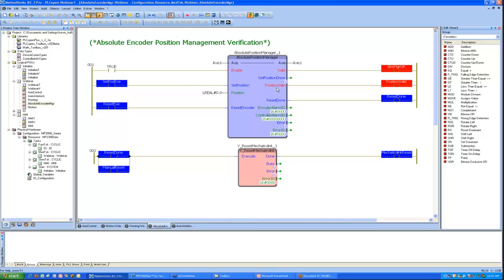What's happening inside this block is there's an MC set position function block, there's a Y reset absolute encoder function block, and there's also a read access alarm function block. So it's kind of taking those three features and combining them into one. And that's a key point to this block being of service, is that you would have to use this block and no other means of resetting the absolute encoder or setting it, because to do so outside of this block would defeat the purpose of its ability to detect and determine if the position is valid.